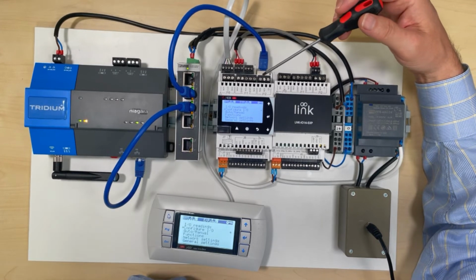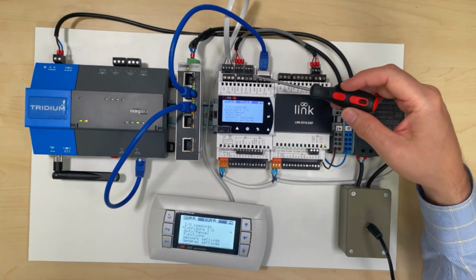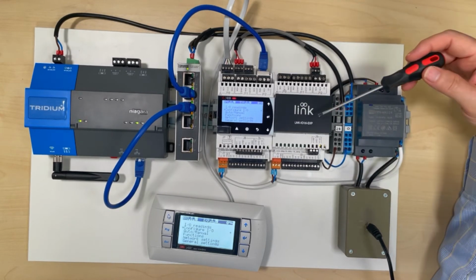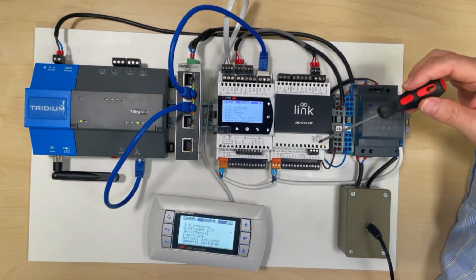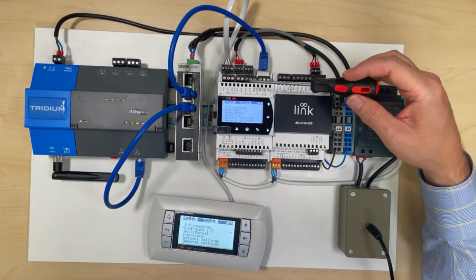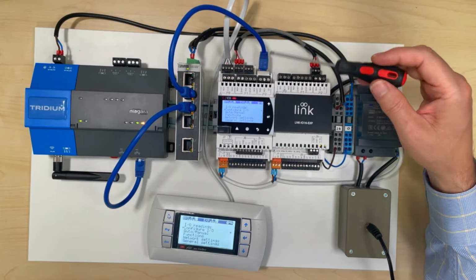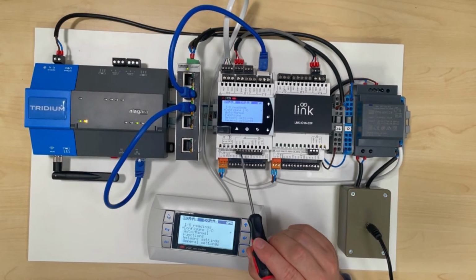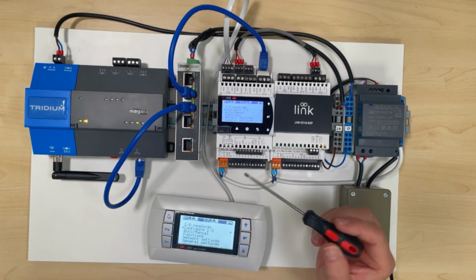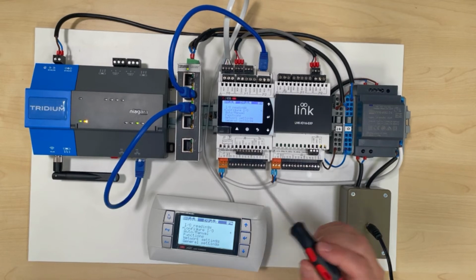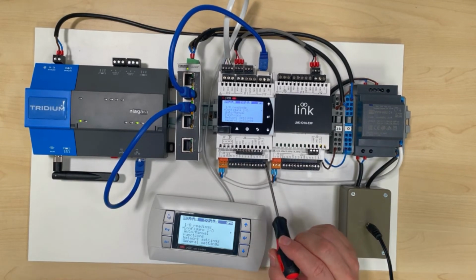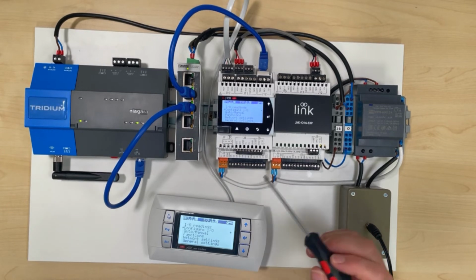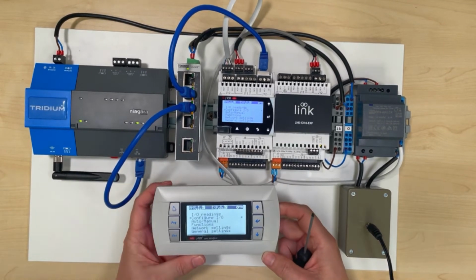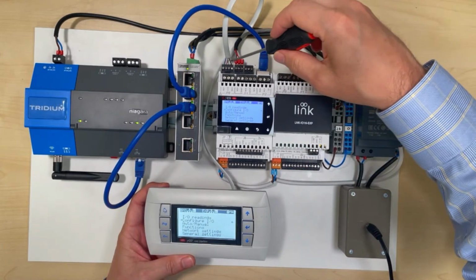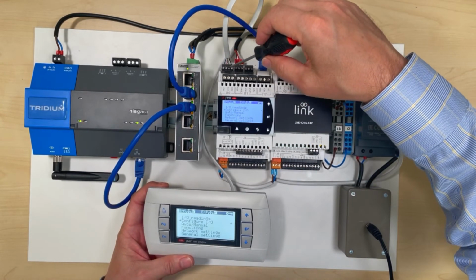only does 1 amp. Now, everything I've said about the IO20 so far applies to all the IOs on the IO16. They work in exactly the same way, with exactly the same limitations. But now I'm going to go on and describe the additional points we've got on the IO20, which are these ones down here. You've got 2 digital inputs. They're not pulse counting, they're purely digital input. And you've got 2 analog outputs. They can be 0 to 10 volt, pulse width modulation, 100 hertz or 2 kilohertz, the same as the universal outputs that we've got down here. So as we said, we've got the optional display here, and as you can see, it just hooks into the IO20 up the top here on this set of terminals.